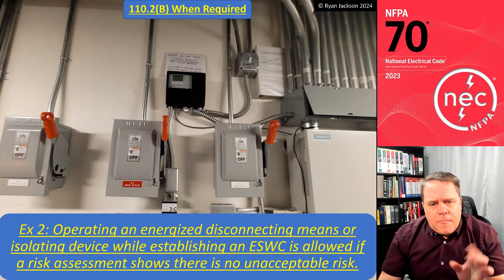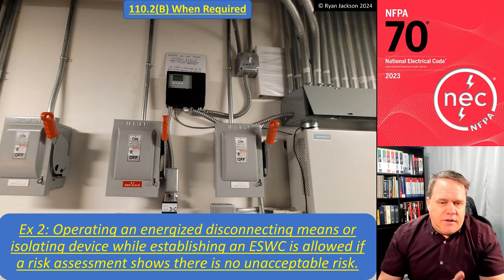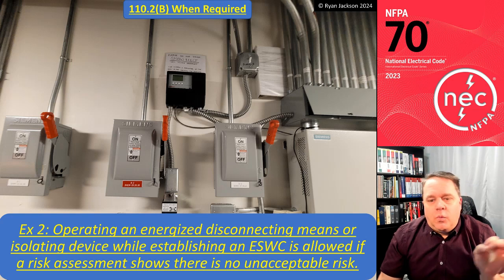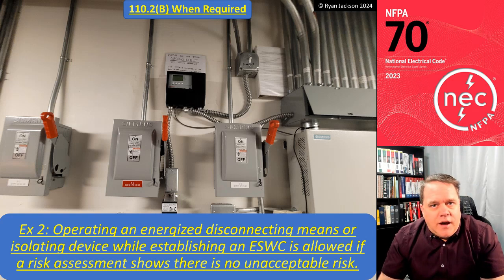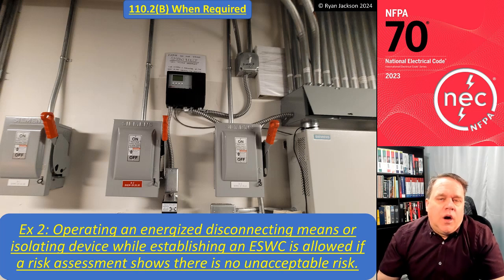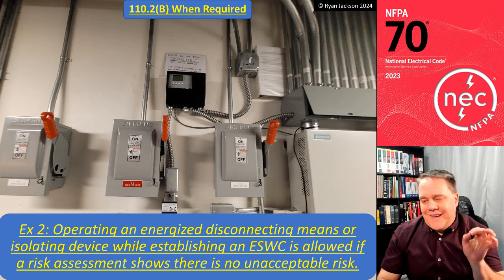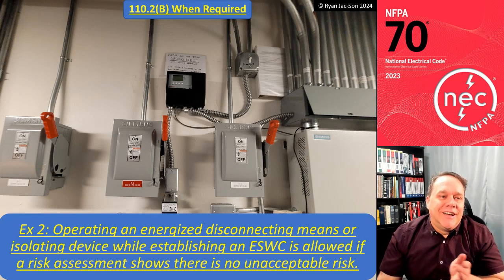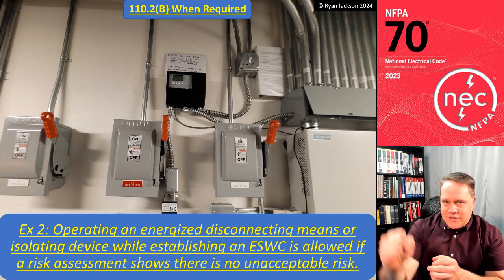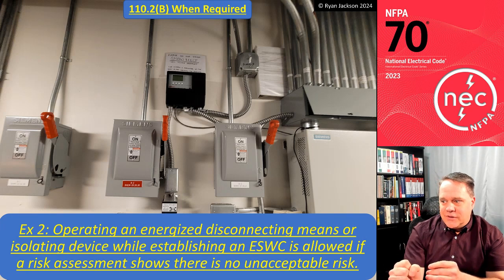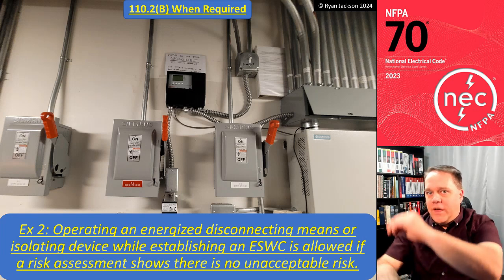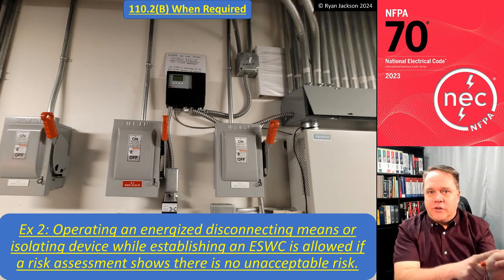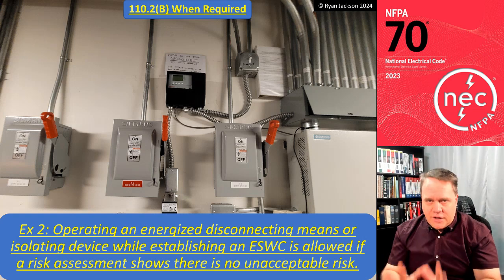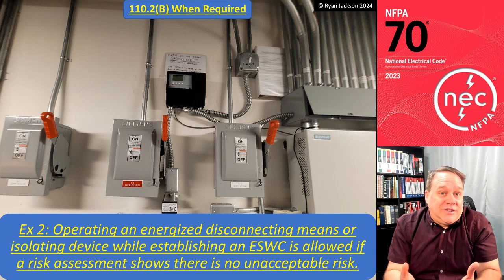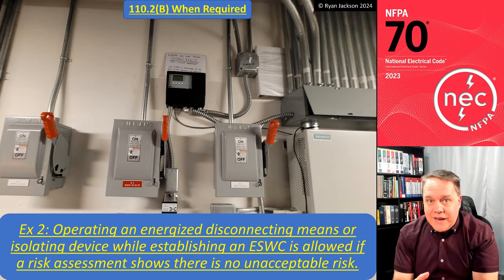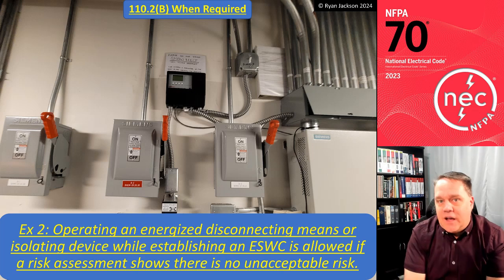Exception 2, and this is new. Operating an energized disconnecting means or isolating device while establishing an electrically safe work condition is allowed if a risk assessment shows that there's no unacceptable risk. All right, well, part of establishing an electrically safe work condition is shutting off the power. So how can I shut off the power? That's working on equipment, and it's not in an electrically safe work condition because you're placing it in. Okay, hang on. You have to be able to shut off disconnects while you're creating an electrically safe work condition. So, yes, can you shut off the disconnect?